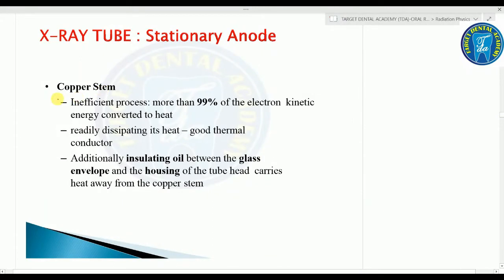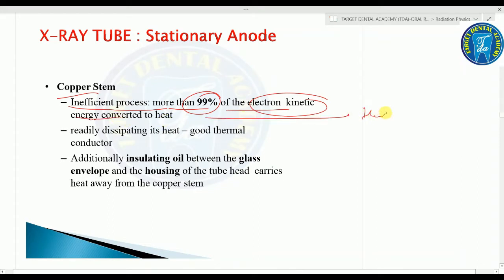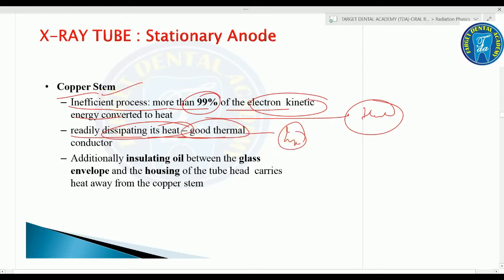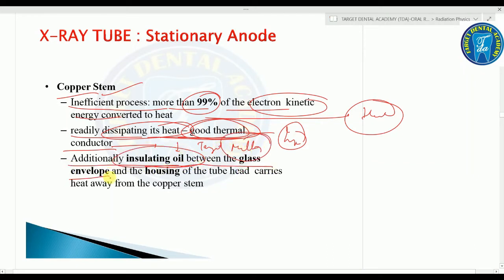More than 99% of the electron kinetic energy is converted into heat. The copper stem is a good thermal conductor that dissipates heat from the tungsten, reducing the risk of target melting. Additionally, insulating oil between the glass envelope and the tube head housing carries heat away from the copper stem.